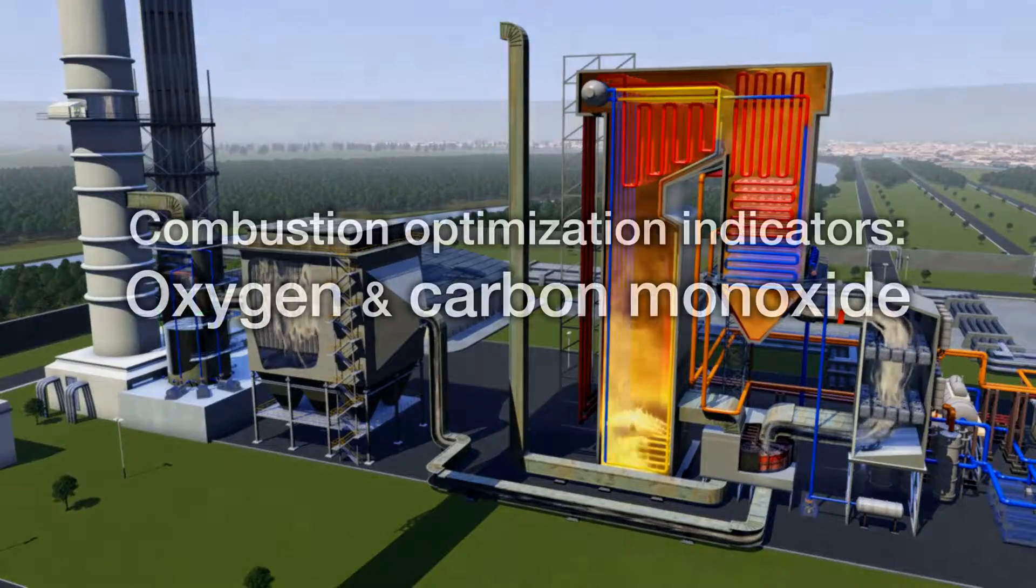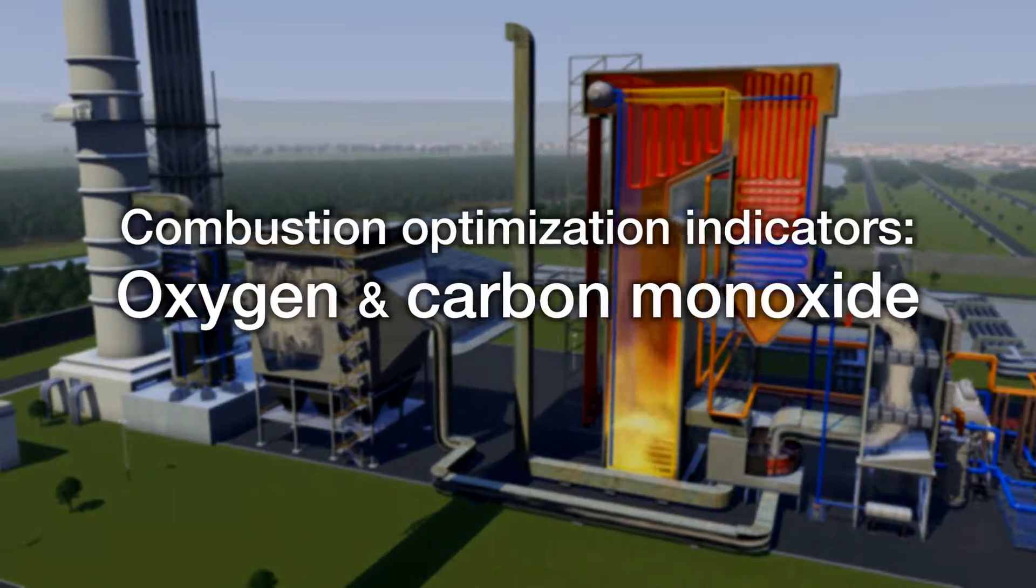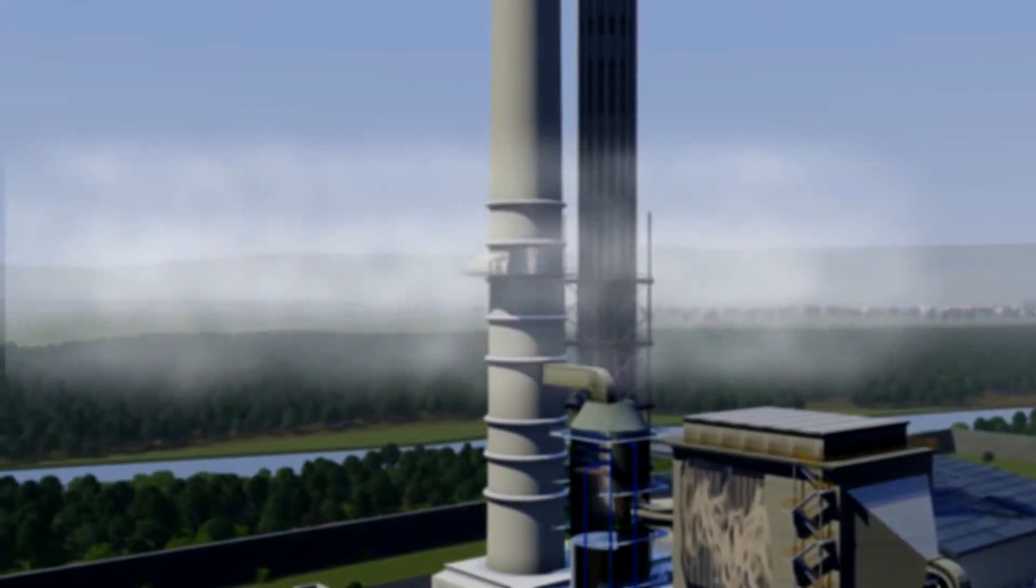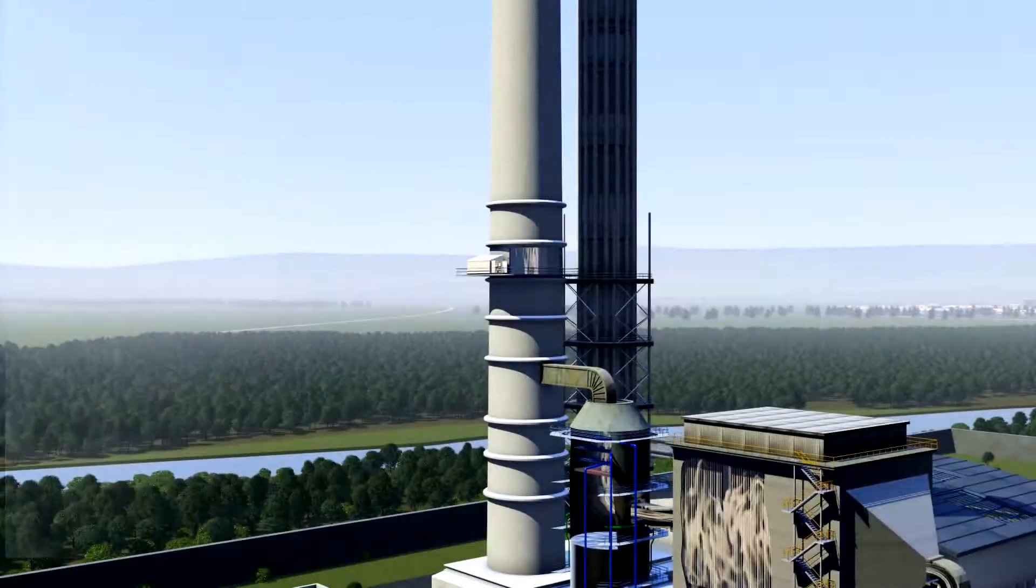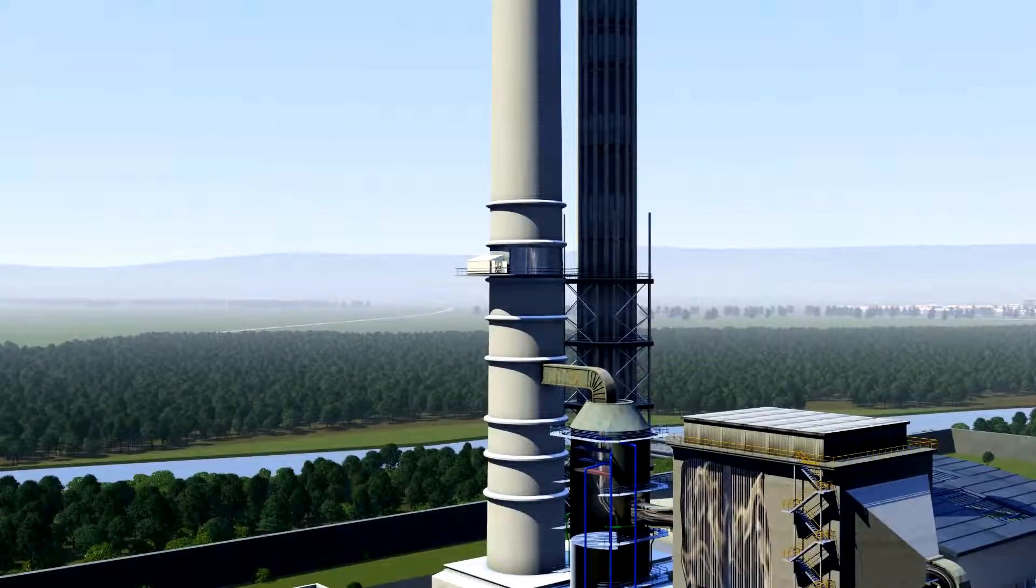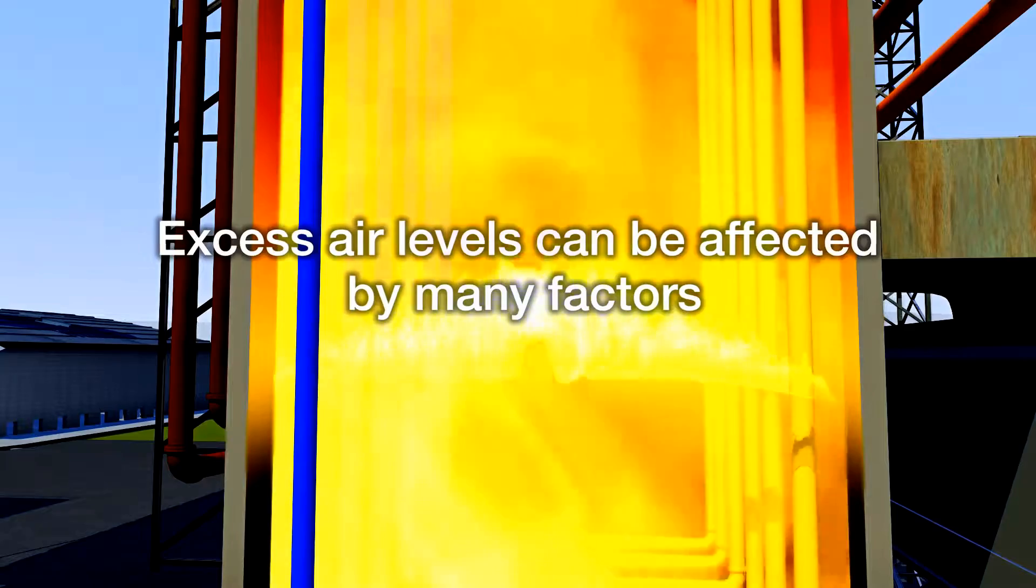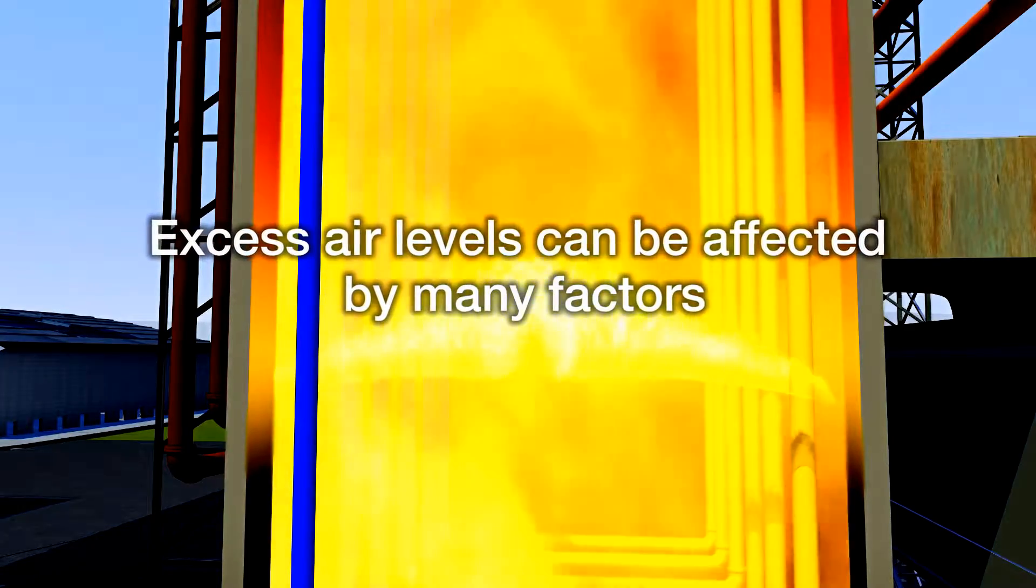Two gases that provide a particularly good indicator for combustion optimization are oxygen and carbon monoxide. Accounting for approximately 21% of the composition of atmospheric air, oxygen provides an excellent indicator for regulating excess air. However, maintaining the correct level of excess air for combustion can be complicated by variations in the fuel and the air.